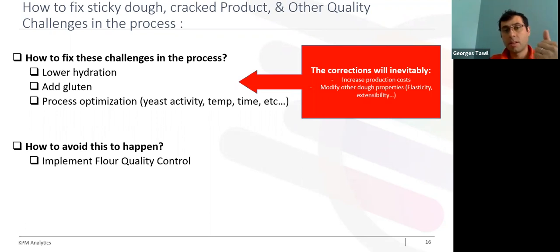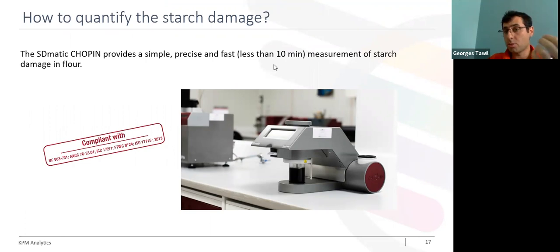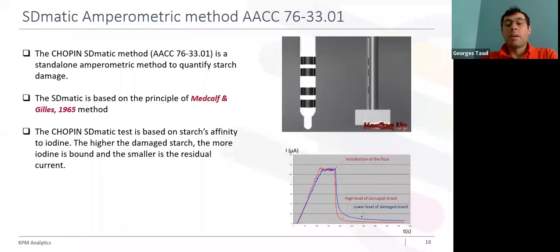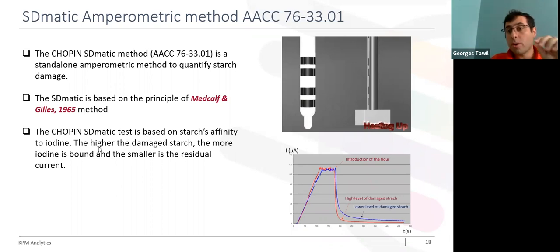Today I would like to propose the SD-MATIC to quantify starch damage. The SD-MATIC provides simple, precise, and fast results — you will have your answer in less than 10 minutes — and this method is compliant with many standards. The principle of the SD-MATIC is based on the method of Medcalf and Gilles. The SD-MATIC measures the affinity of starch to iodine: the higher the damaged starch, the more iodine is bound to the starch, and the smaller the measured residual current.